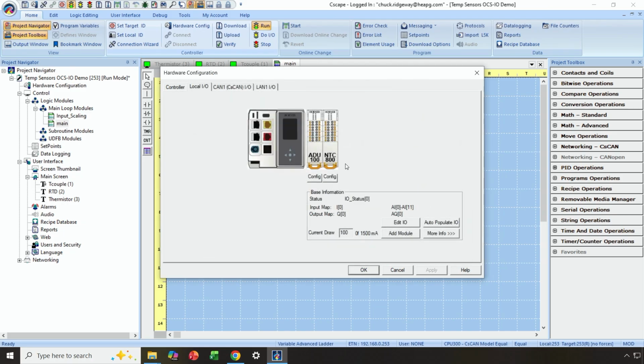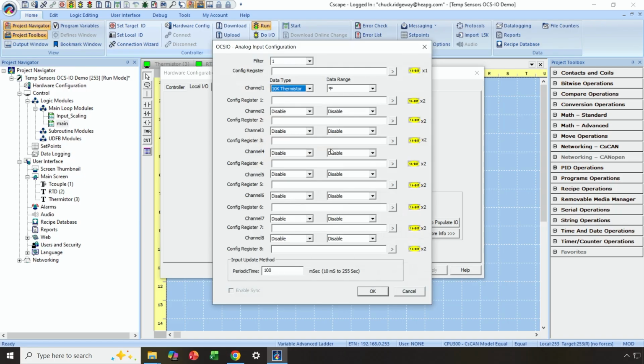And then in terms of the thermistor input module, it only supports the 10K thermistors of type 3, so there's really nothing to select from the pull-down list except thermistor or disable. And you can select between degrees F and degrees C, and this reports in hundredths of a degree increments. Not because it has any more resolution, just because it's a much more limited temperature range. So we chose that method of reporting the data. Okay, and we again have one sensor connected and the rest are disabled, so we don't get any false alarm conditions that occur in that scenario.